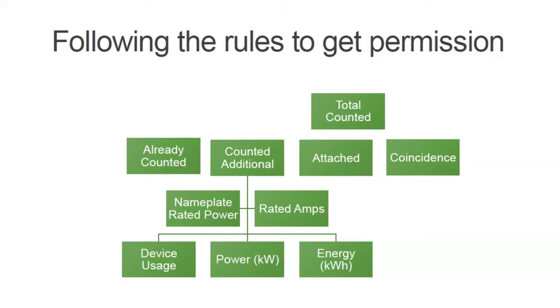Looking at the row above, we tend to look at equipment in the nameplate rated power and the rated amps. That's where it will move up and be operating, and where they think it's going to operate at its full usage. These kinds of things count in the counted additional box there, and to the left you see the already counted. I mentioned the 3 watts a square foot for lighting and plug loads, so that stuff's already counted. Also, kitchen countertop loads are already counted, things like that.